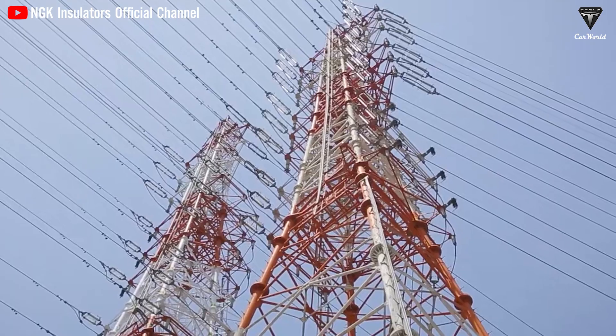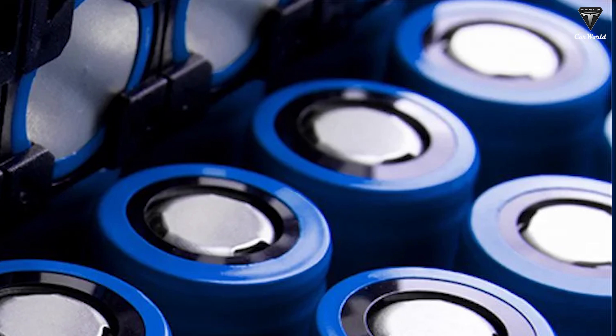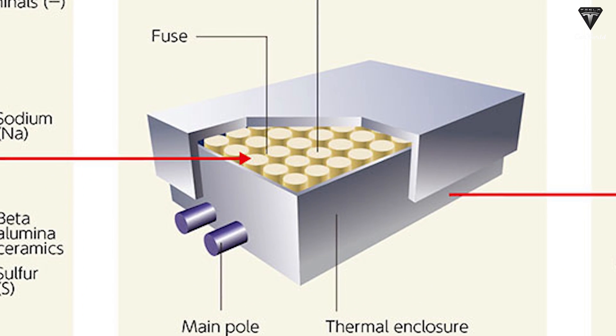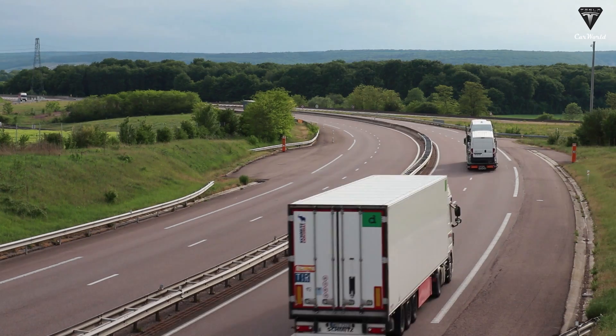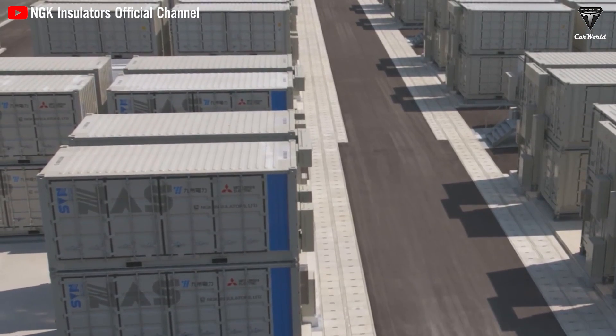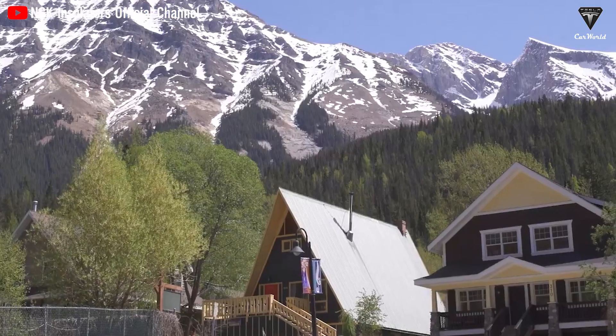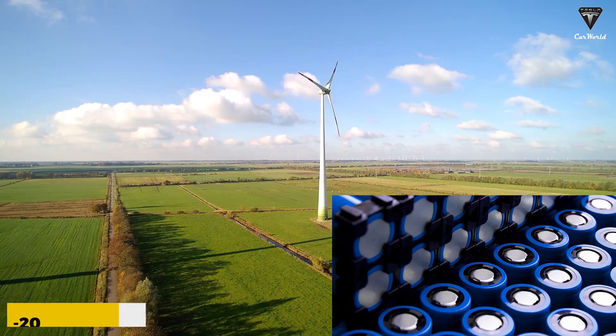The 200 kW / 1,200 kWh battery is compact and easy to store, available in a 20-foot ISO shipping container. Thanks to fully containerized battery units, clients can save money on transportation and construction. The NaS battery has less capacity deterioration and no need for battery replacement until the end of its life — about 15 years or around 4,500 cycles.